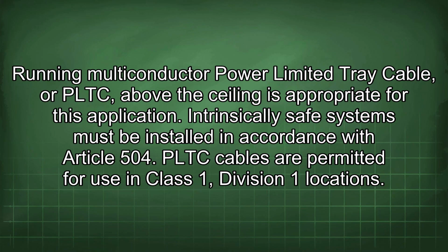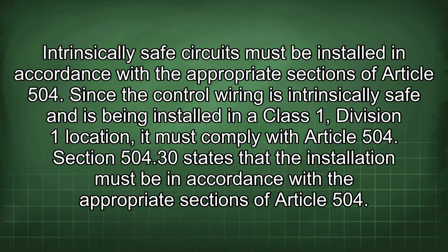Running multi-conductor power limited tray cable, or PLTC, above the ceiling is appropriate for this application. Intrinsically safe systems must be installed in accordance with Article 504. PLTC cables are permitted for use in Class 1, Division 1 locations. Intrinsically safe circuits must be installed in accordance with the appropriate sections of Article 504.